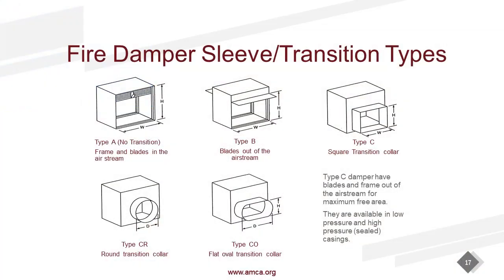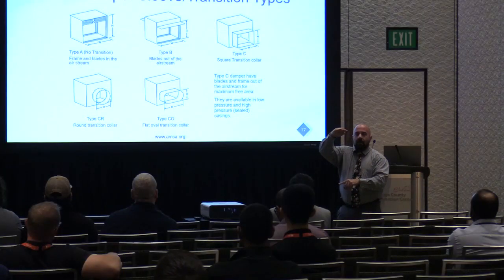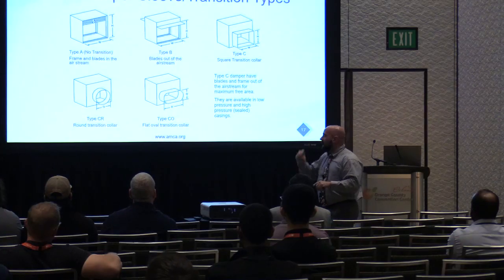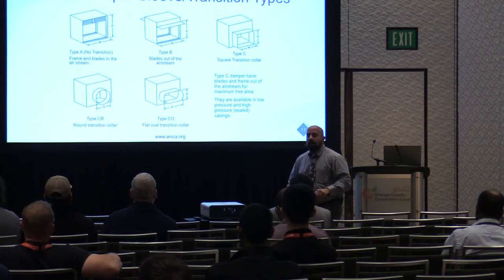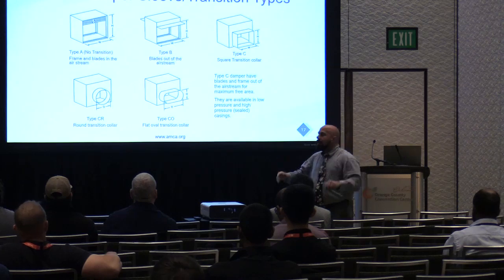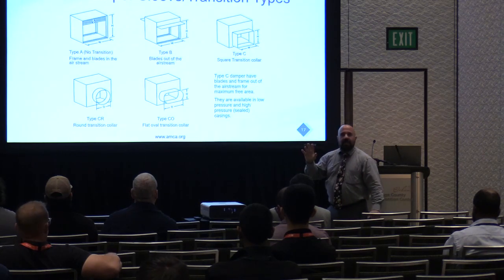What it does is it grows the height of the damper 2, maybe 3 inches, depending on the size. It puts a transition, we call that a hi-hat. Think of a top hat, Mr. Peanut. And it takes that blade pack out of the airstream. So you still have a 12 by 12 duct opening to attach your duct to, but your wall opening is now going to grow in order to accommodate that transition, that blank off, that hi-hat. So maybe it's 12 by 14. So the unit cost of that damper went up a little bit, but we call these about 96 to 98% free area. They do pretty well in pressure drop.